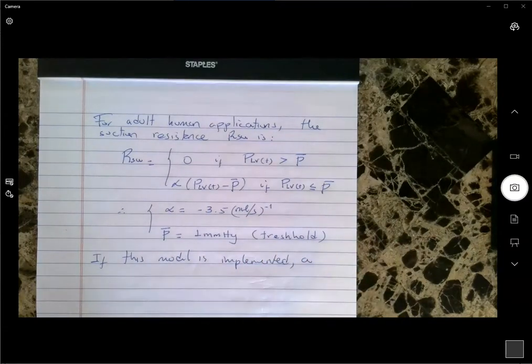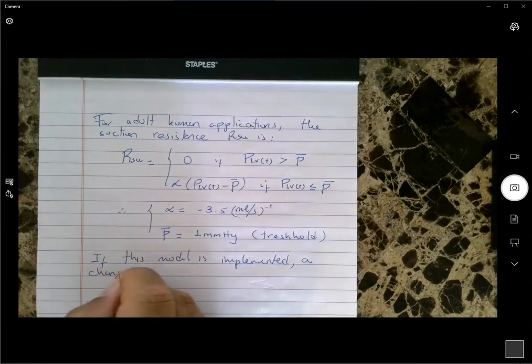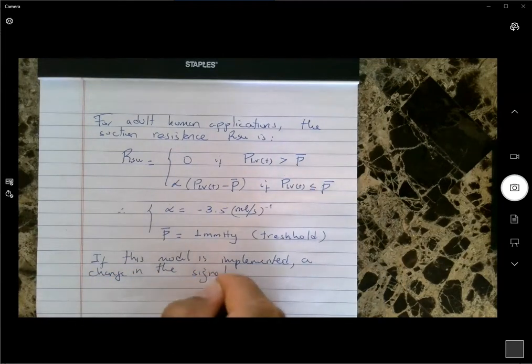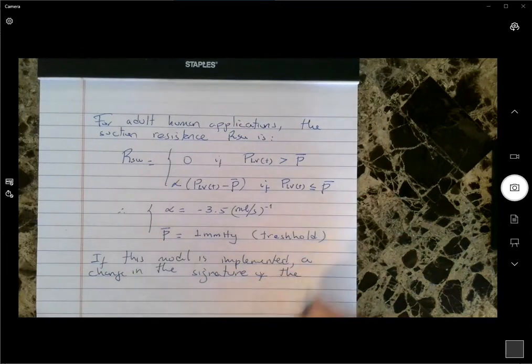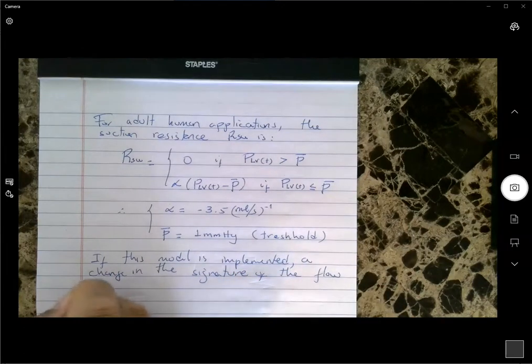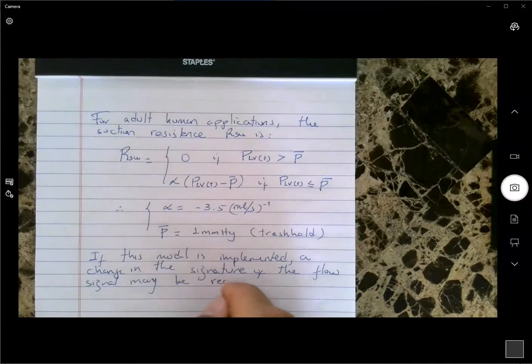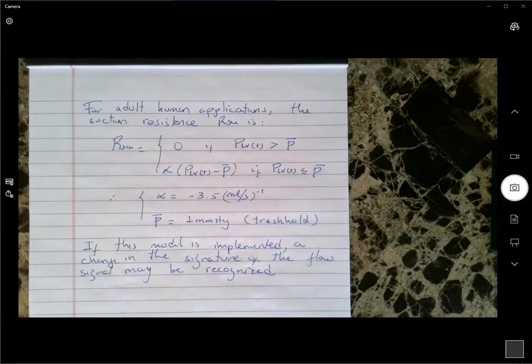a change in the signature of the flow signal may be recognized. So if you introduce this additional resistance that changes as the pressure conditions change, there will be a change in pattern in the signature of the pump flow. So instead of having a specific frequency, you'll see a couple of underlying harmonics or underlying frequencies attached to that.